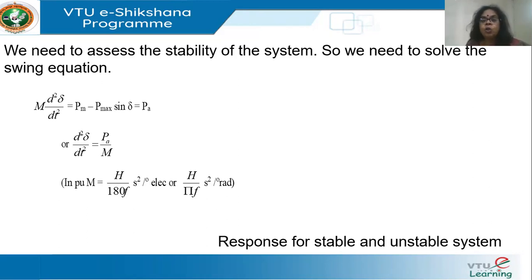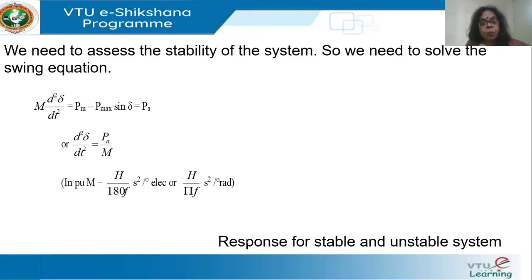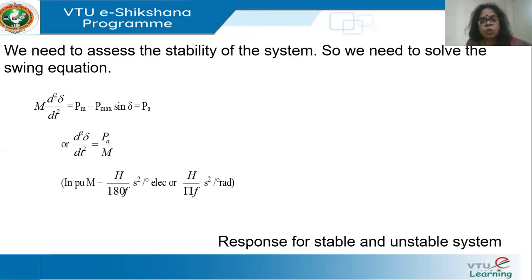The turbines are large and do not change as fast as the load on the electrical side. Disturbances come mainly from rapid changes in load, load rejection, sudden increase in electrical load, or electrical faults. The swing equation contains a sine delta term, making it a non-linear equation, and it is virtually impossible to get a closed-form solution. Hence we resort to numerical methods.